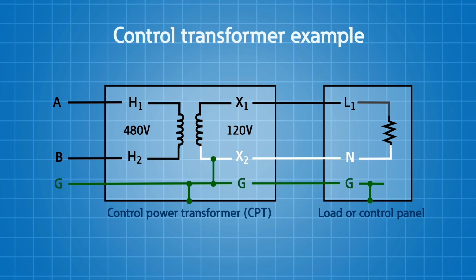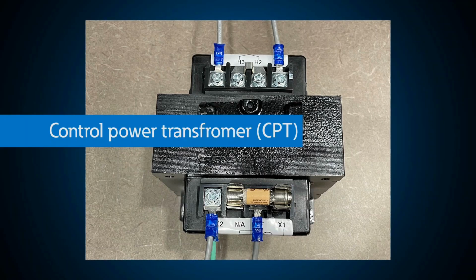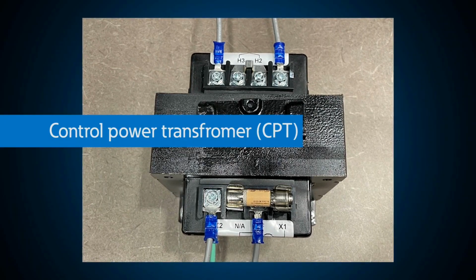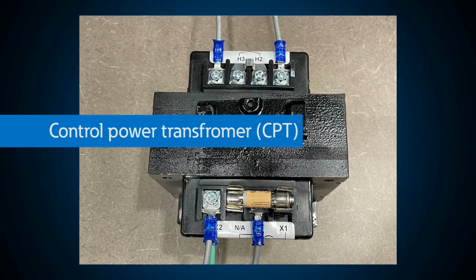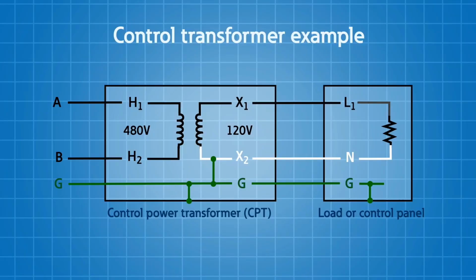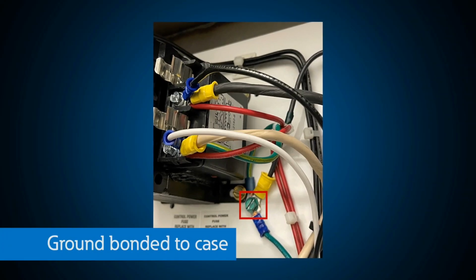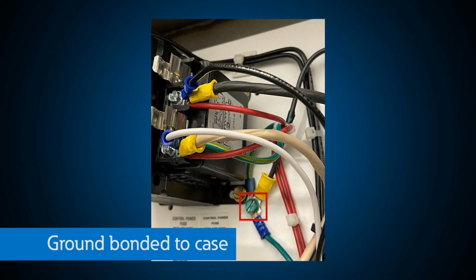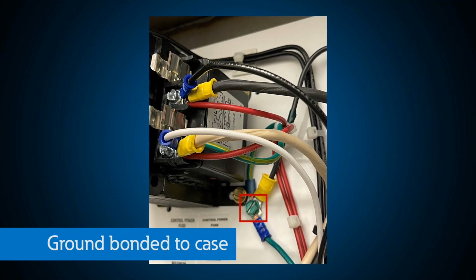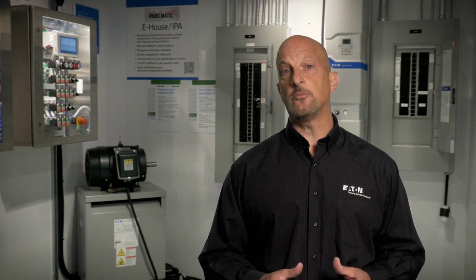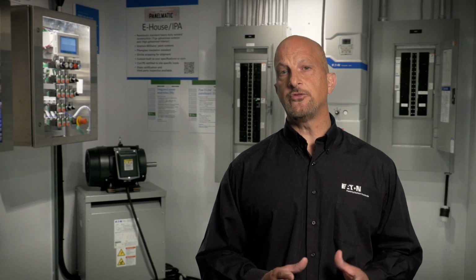For this situation, a simple wire connecting X2 to the incoming ground wire coming from the primary of the transformer would suffice for a control power transformer. This ground would also be bonded to the transformer case to ensure that the case and all metal parts remain at a constant potential for reference to the known ground conductor. I've seen many instances where this ground connection was not made, supposedly to make it better for power quality reasons, but it almost always made it worse, and electrical equipment was damaged.